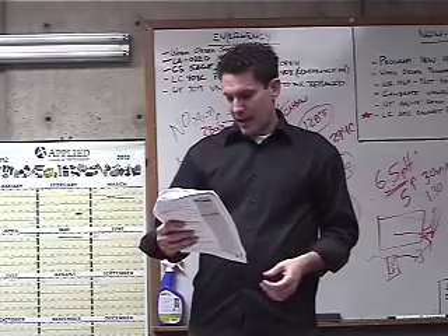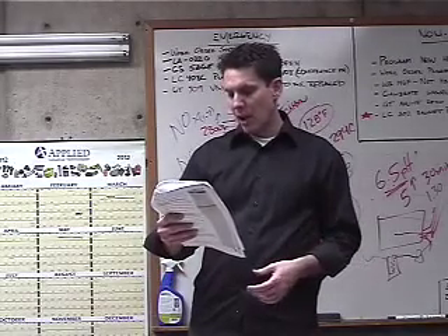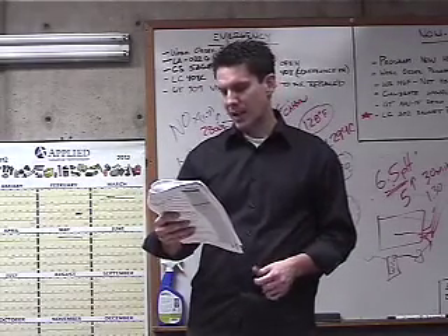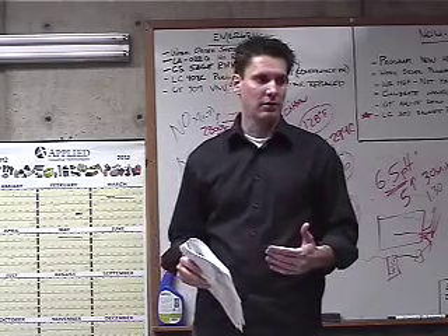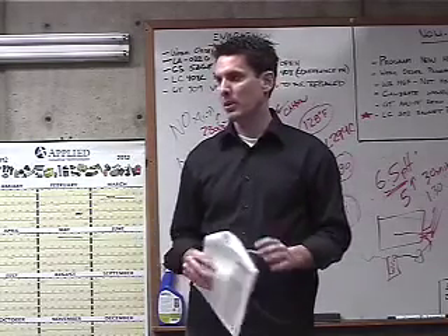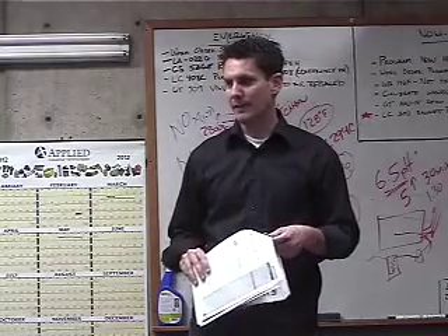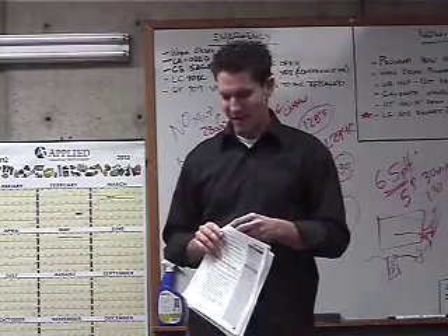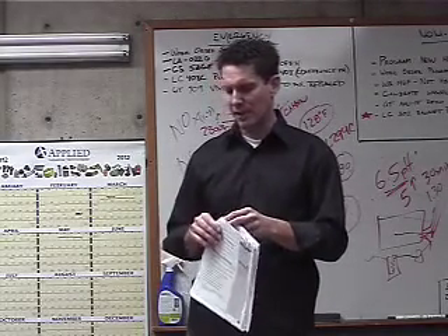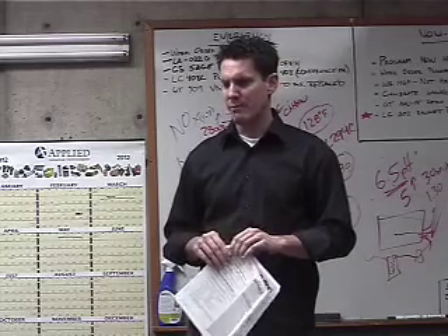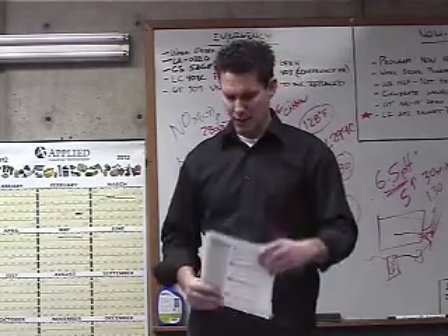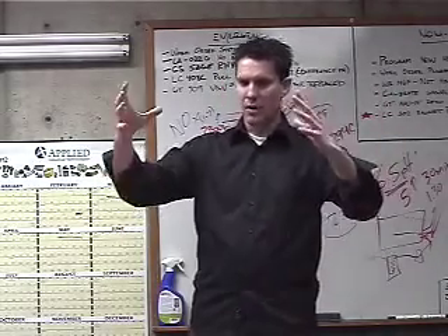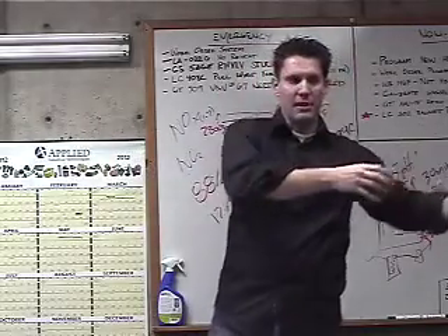All right, monthly. Monthly inspections should include the following. Test the high limit control. You want to make sure that your high limits aren't going to fail. You guys have seen the results of boilers exploding before? That's pretty simple. In our boiler class we've got some pictures of these boilers at Mary's Hospital back east. The big boiler lifted up, went outside the building, and was resting in the parking lot.